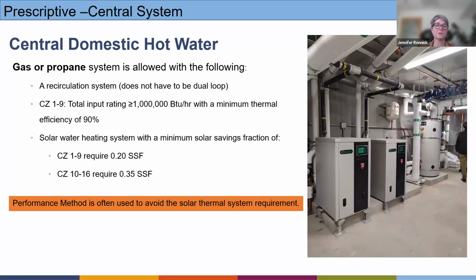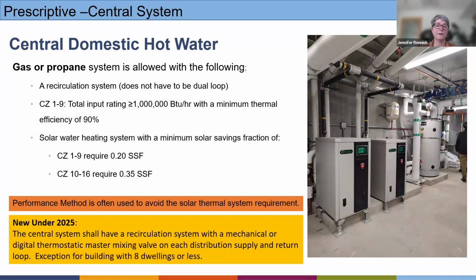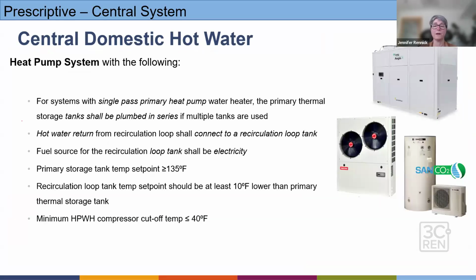So yes, you could still install your gas system prescriptively, but under the new 2025 code, there is some explicit language about prescriptively having a mechanical or digital thermostatic master mixing valve on each distribution. So kind of in the weeds there, but the idea is, yeah, you can still do the gas. You're supposed to have a solar savings fraction or some solar thermal component, but you can use the performance method and trade that off, which is really common.